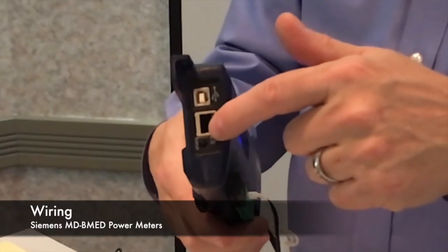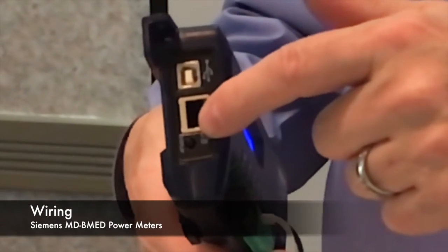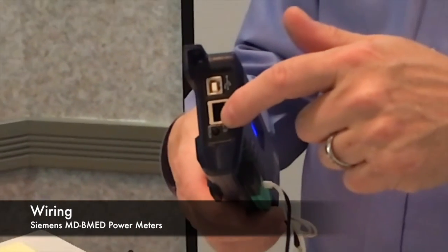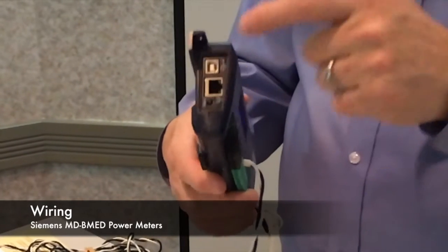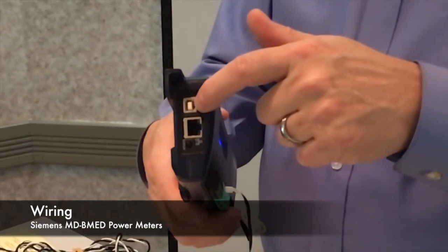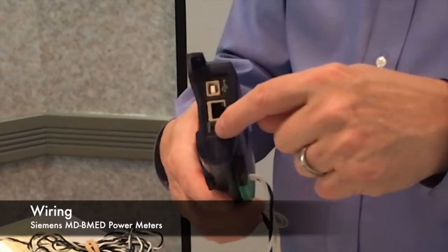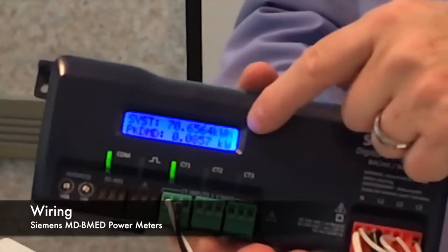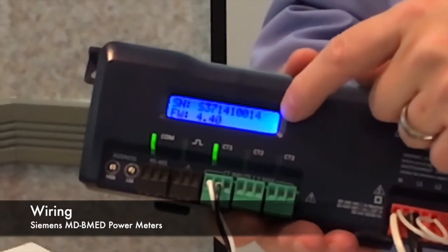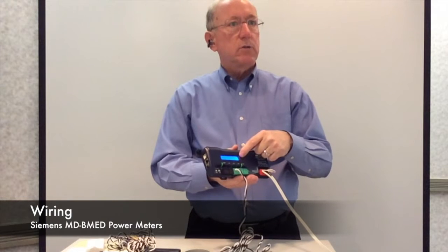On the side, you have your Ethernet connection if you choose to use Ethernet TCP, or BACnet IP or Modbus TCP, and a USB connection, which uses a standard USB type AB cable for connecting to your laptop to run the free Viewpoint software for further analysis on the meter itself. An additional button is on the side of the meter that allows you to lock in a particular screen of the rotating screen on the meter, which provides a visual content of all the active meter data.